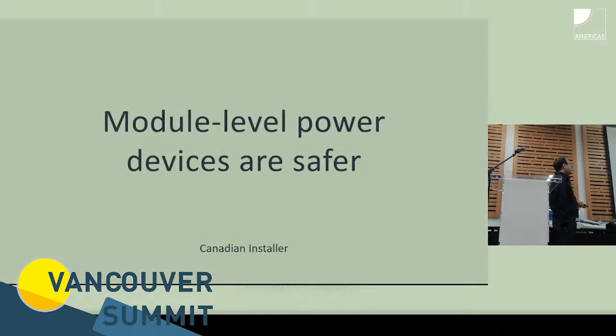Now another common misconception is that module level devices are safer. Are they? Why not? With 240 volts you could get burned or worse, but at a lower voltage you're not going to get killed the same way. You're working with the open circuit voltage of one PV module, which is maybe 40 to 60 volts at most, and one string's worth of short circuit current, which is just one PV panel's worth. So shouldn't it be safer?